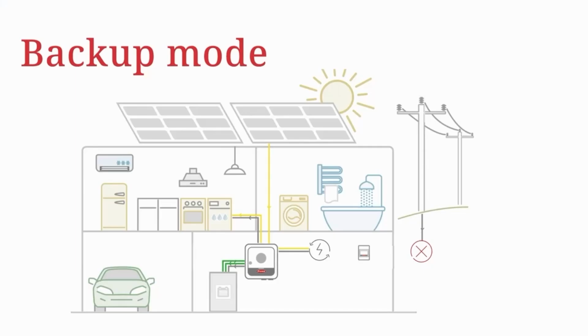In backup mode, we can install a device which stops energy being generated flowing back to the grid, protecting those workers that will be re-establishing the connection. However, it enables the inverter to stay active, drawing energy from the panels and also powering your supplies within the property. Potentially as well, you can charge your battery and ensure that you have energy being topped up into that battery for the evening when you may need it in darkness.